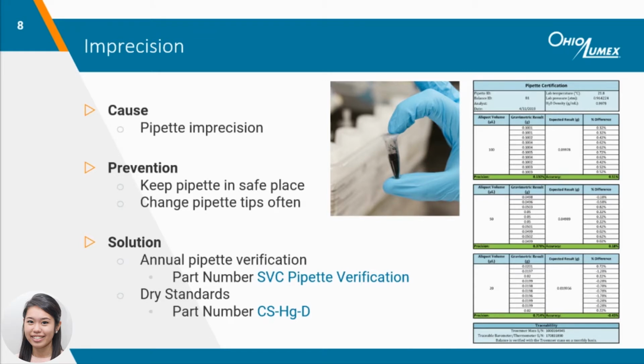The dry standards are all in one, meaning we cut out the need for carbon and pipetting, so the dry standard can be directly dispensed into a ladle and covered with soda. These are also super helpful for those who perform analysis in the field like I do. I never have to worry about transporting liquid standards anymore because dry standards are not considered a hazardous material.